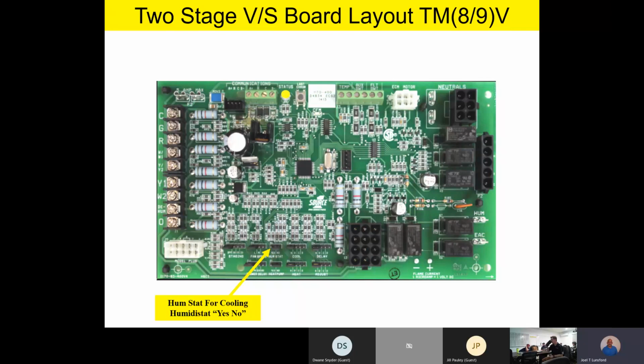If you're not going to use that function, double check during your startup and commissioning that the humidistat jumper is in the no position if you don't want to use that function. Right below that, you've got your heat pump, yes, no. And again, this configures the board for an O terminal for a heat pump.